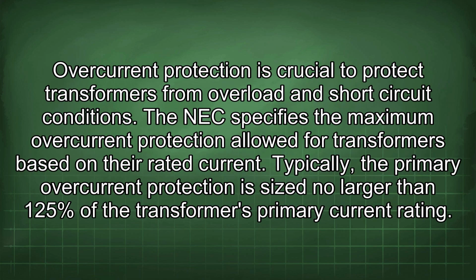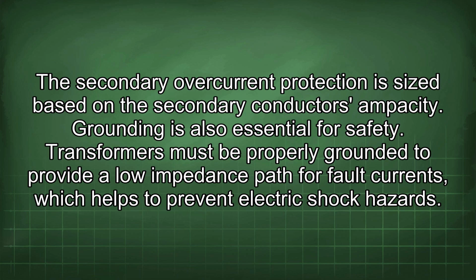Overcurrent protection is crucial to protect transformers from overload and short-circuit conditions. The NEC specifies the maximum overcurrent protection allowed for transformers based on their rated current. Typically, the primary overcurrent protection is sized no larger than 125% of the transformer's primary current rating. The secondary overcurrent protection is sized based on the secondary conductor's ampacity.